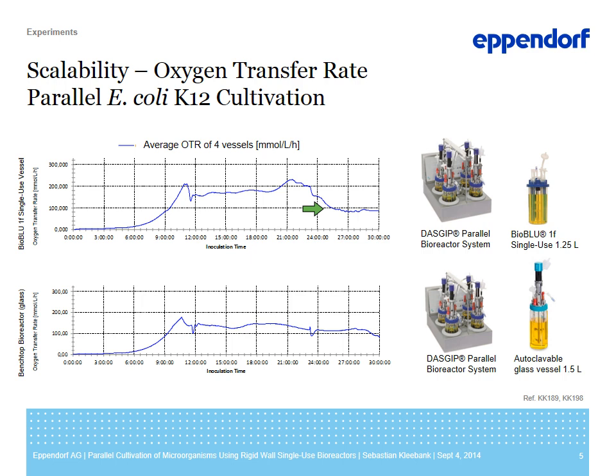Now for comparison, we applied exactly the same process to our autoclavable glass bioreactors. And on the lower graph you see that the oxygen transfer rate graph is comparable to the graph from the BioBLU 1F reactor. And after we started the feeding here, you see that we reached oxygen transfer rate values between 100 and 150, so a little less than in the BioBLU 1F reactor.